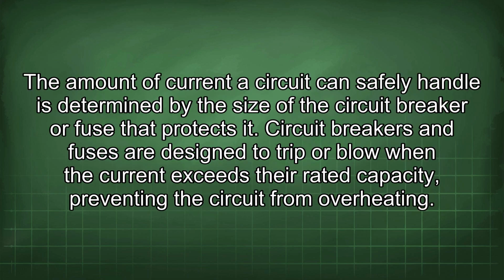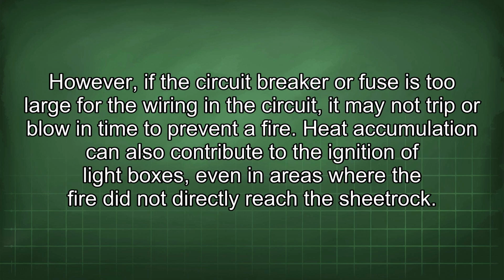The amount of current a circuit can safely handle is determined by the size of the circuit breaker or fuse that protects it. Circuit breakers and fuses are designed to trip or blow when the current exceeds their rated capacity, preventing the circuit from overheating. However, if the circuit breaker or fuse is too large for the wiring in the circuit, it may not trip or blow in time to prevent a fire.